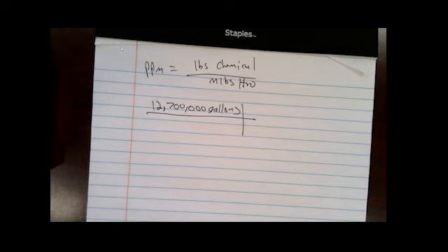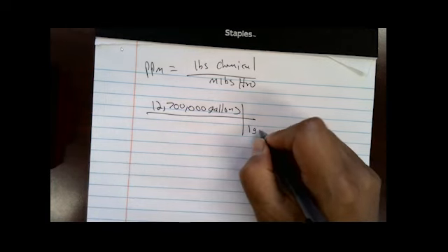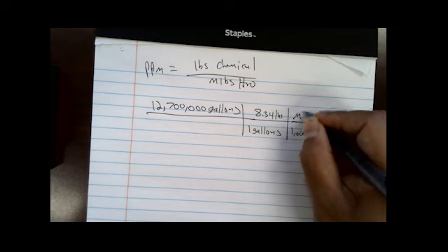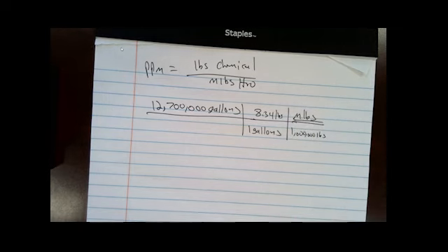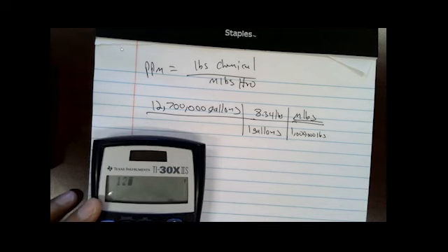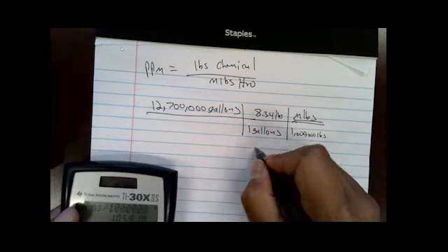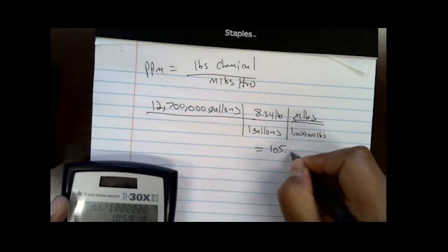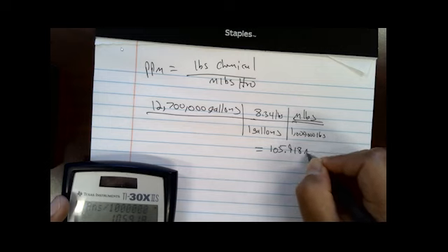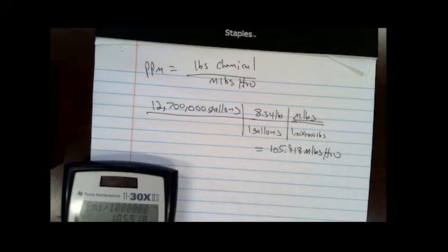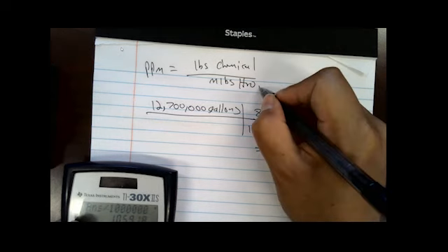So if we look at our conversion factor, 1 gallon is 8.34 pounds. We arrange it accordingly, and we also convert to million pounds, which is what we need to input into the equation, right? So we have 12,700,000. Multiply that by 8.34, right? And then we divide that by 1 million. That gives us 105.918 million pounds of water, right? And we have that first portion. We have the million pounds of water.